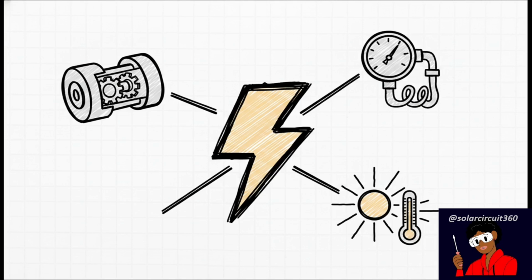First up is the compressor design itself. Second is the refrigerant pressure, specifically something called the head pressure equalization delay. If your compressor tries to start against really high, unequalized pressure, that surge is going to last longer. And third, basic ambient conditions, like the outside temperature, play a role too. It's a highly dynamic, shifting event.